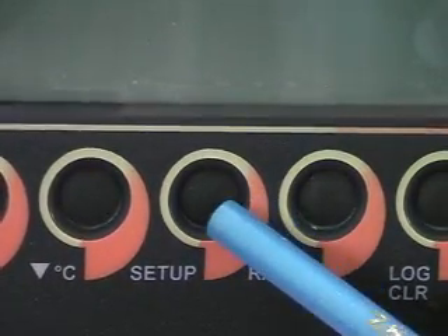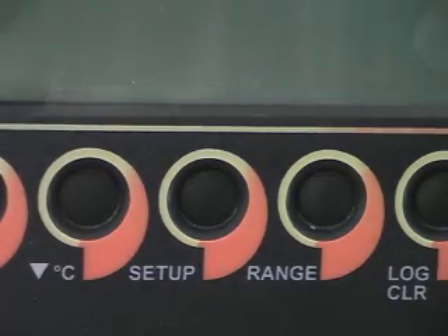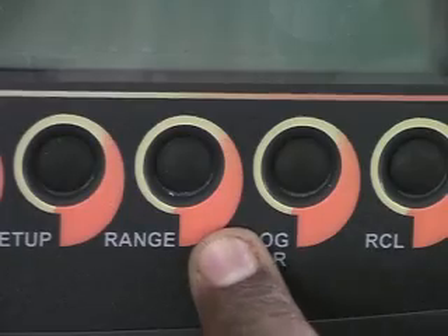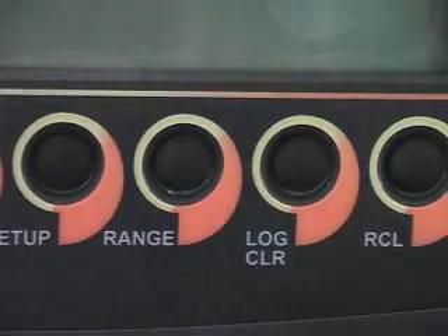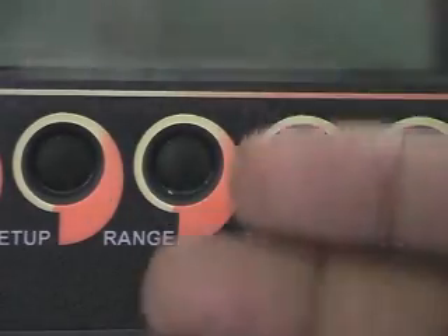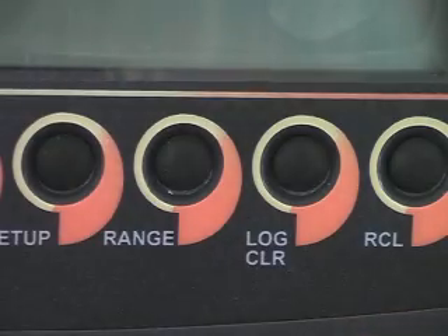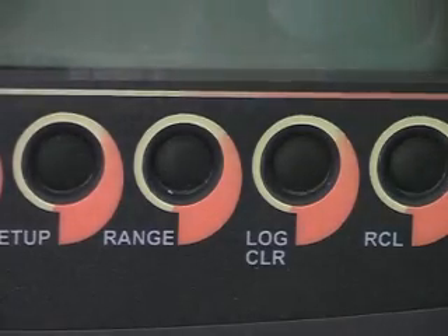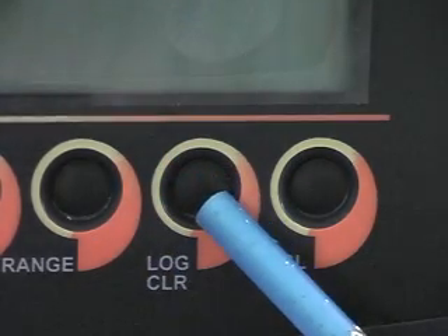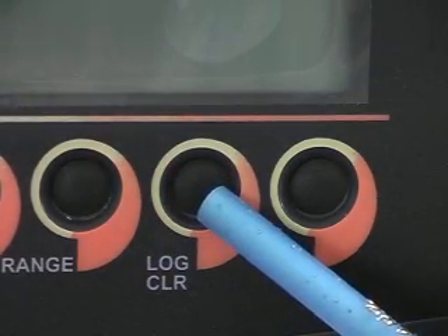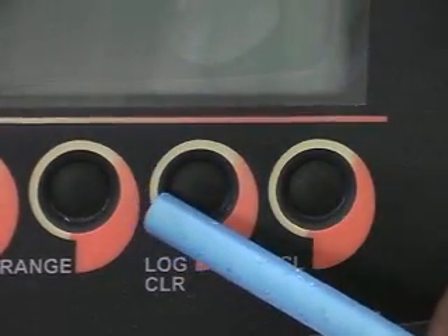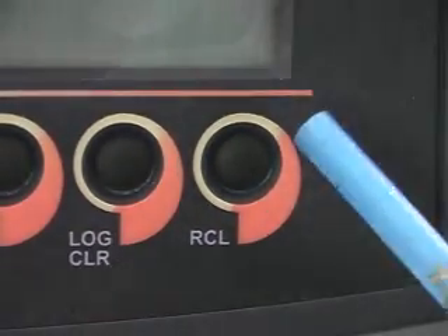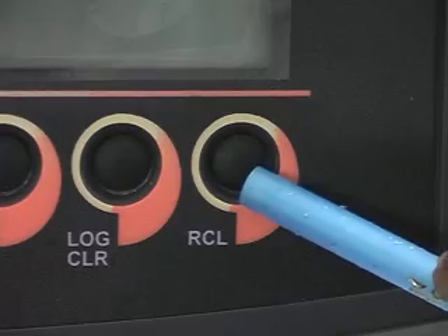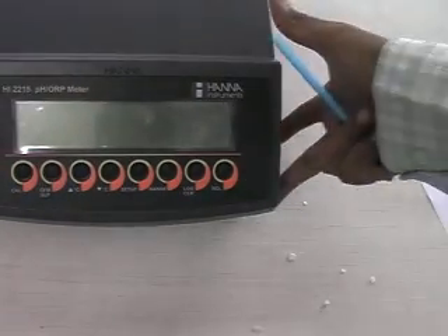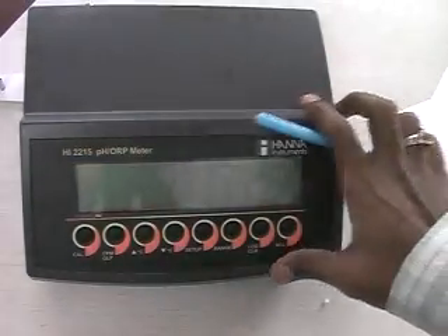Then the next one is the setup key, to enter or exit the setup mode. Then this is also an important key, the range key, to select the measurement range, switch to focus data in setup, or toggle between buffer value and temperature during calibration. You can select your desired range like pH, millivolt, relative millivolt. Then the next one is the log CLR key, to store a value into the memory, to clear pH calibration, or to delete the log data. And the last one is the RCL, to recall the memory. So this is the front panel of this HI2215.